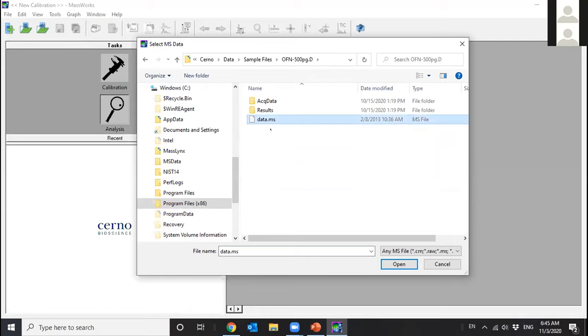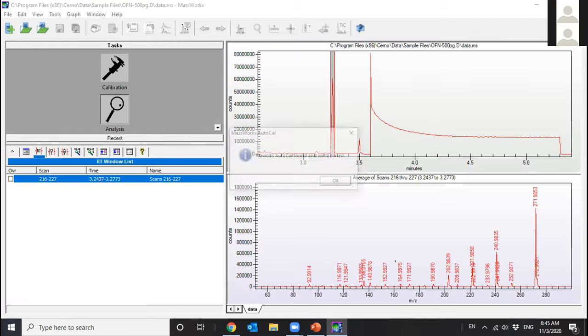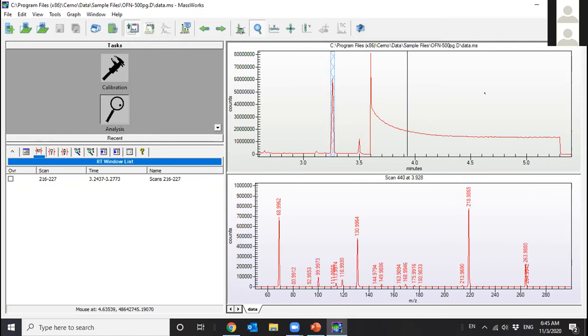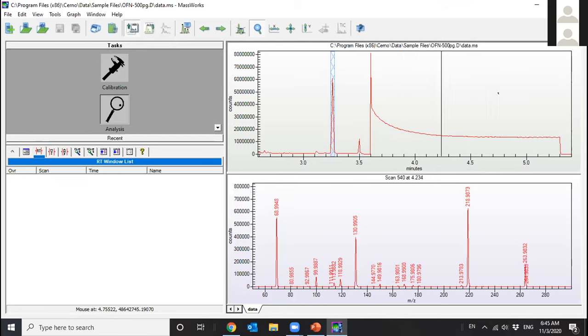And once you open the MS data, it will perform a calibration if a prior calibration does not exist, or it's going to use a prior calculated calibration based on the PFTBA that's included in the run. So in this case, a prior calibration has already been established, by using the calibration gas that's included in the run, and it already applied the calibration, so you can actually click anywhere in the GC trace, the TIC chromatogram, it'll give you the accurate mass for all the peaks.